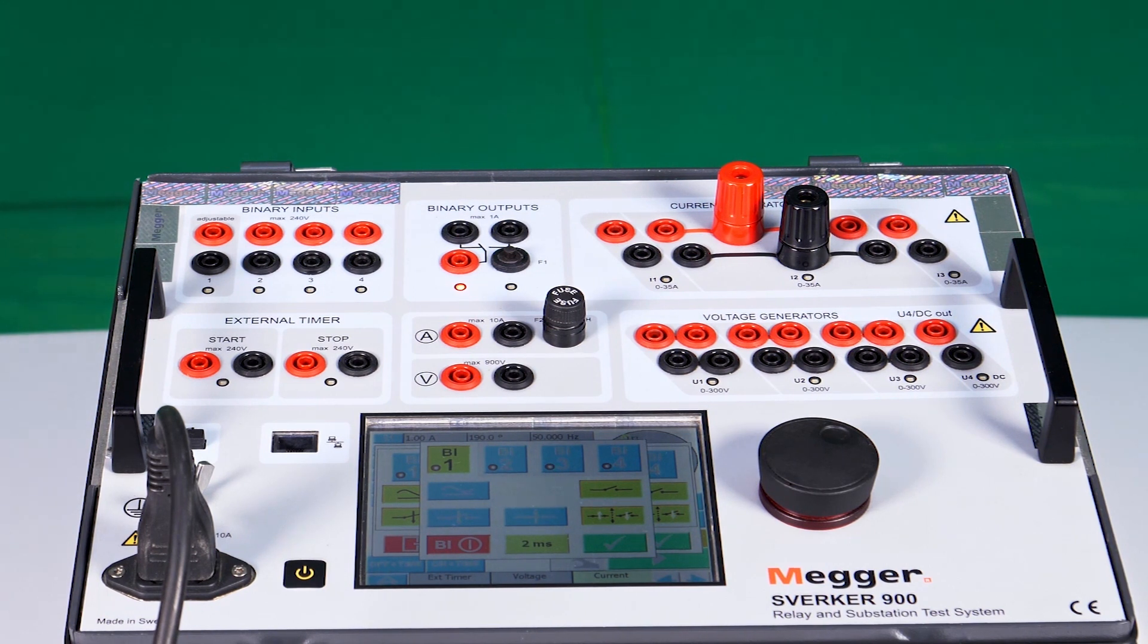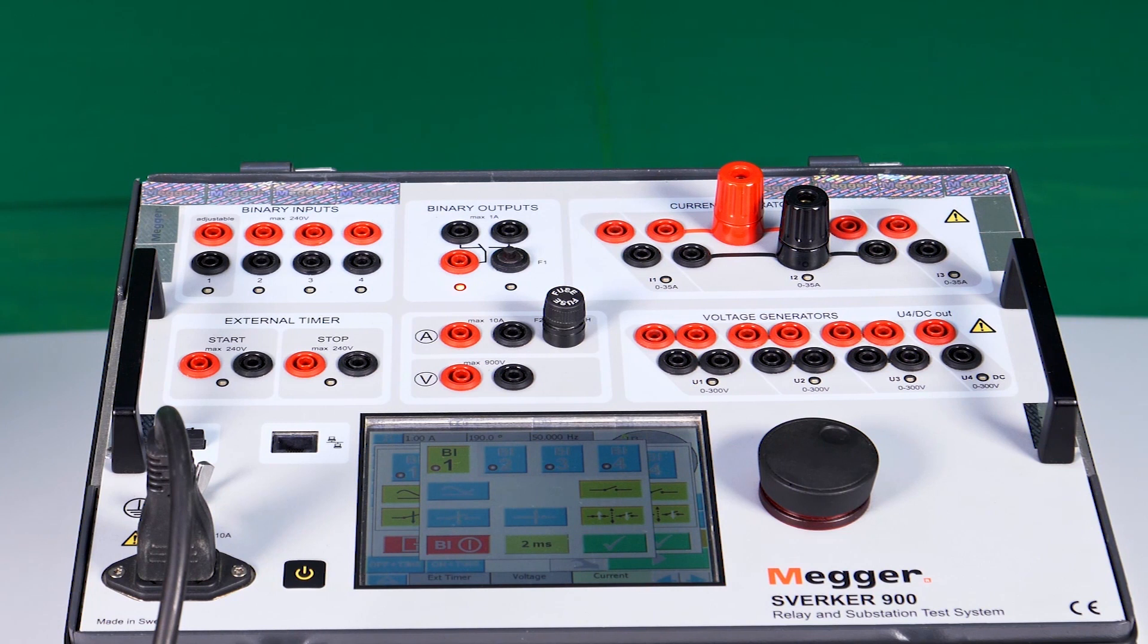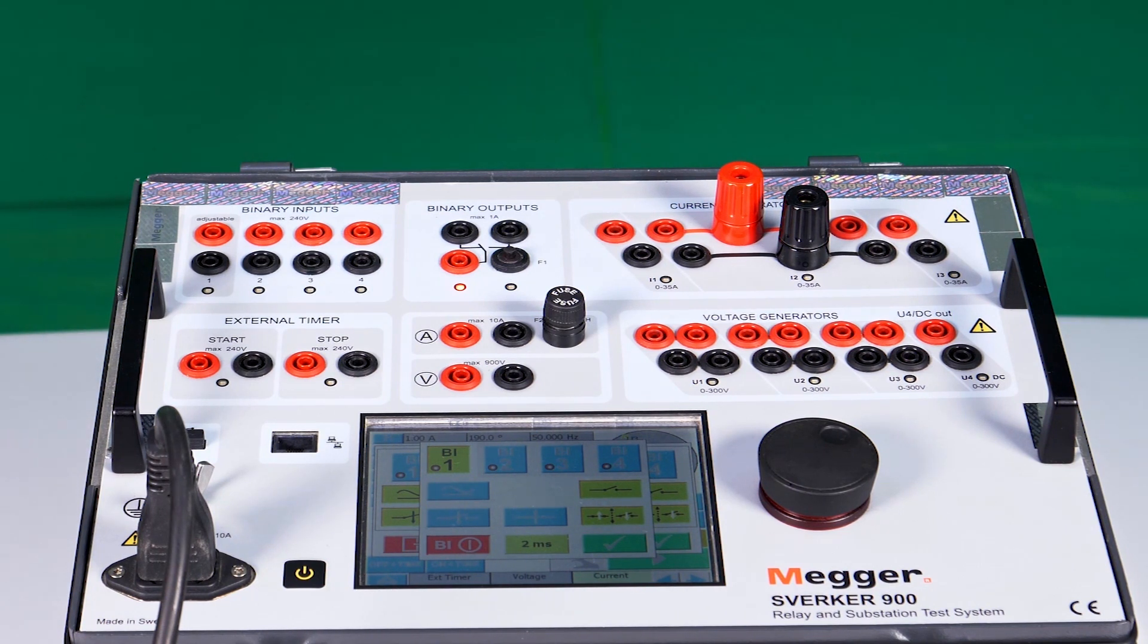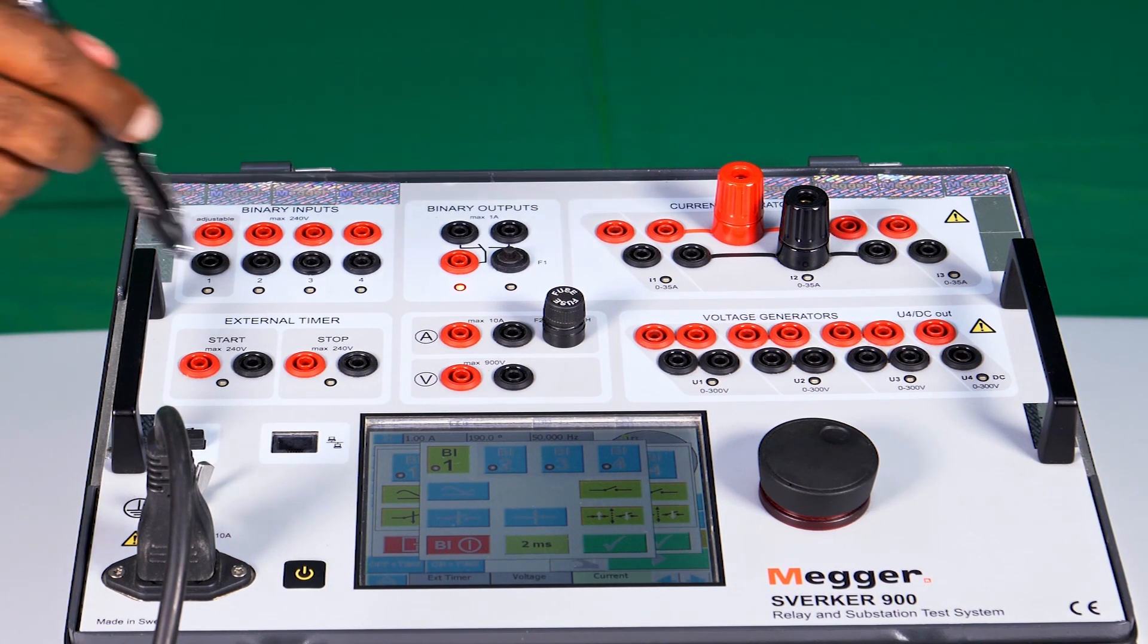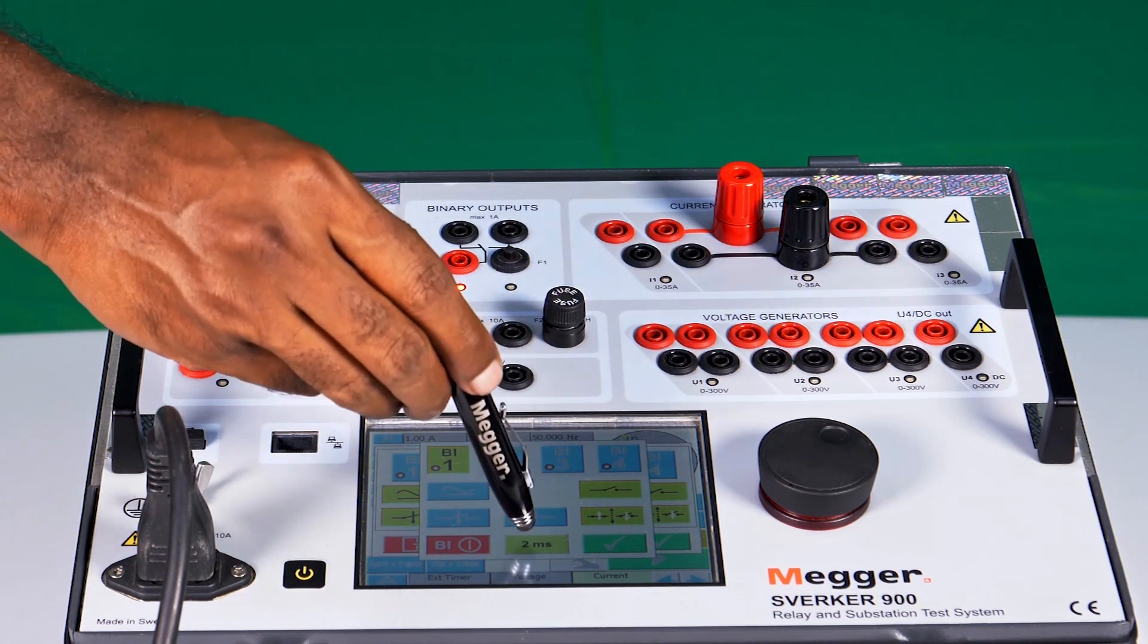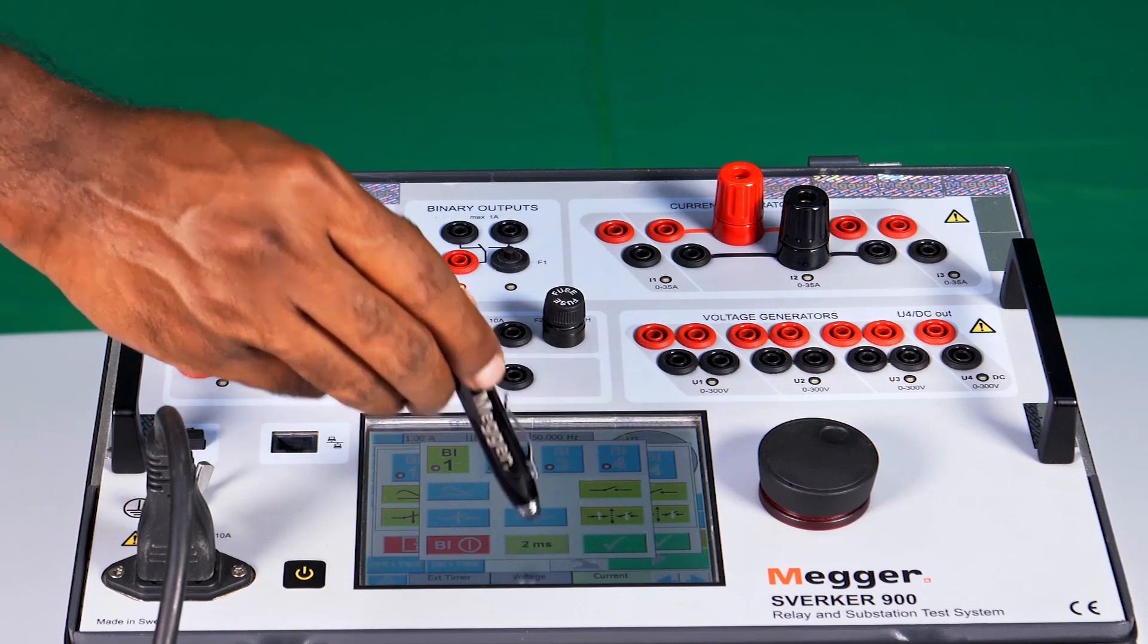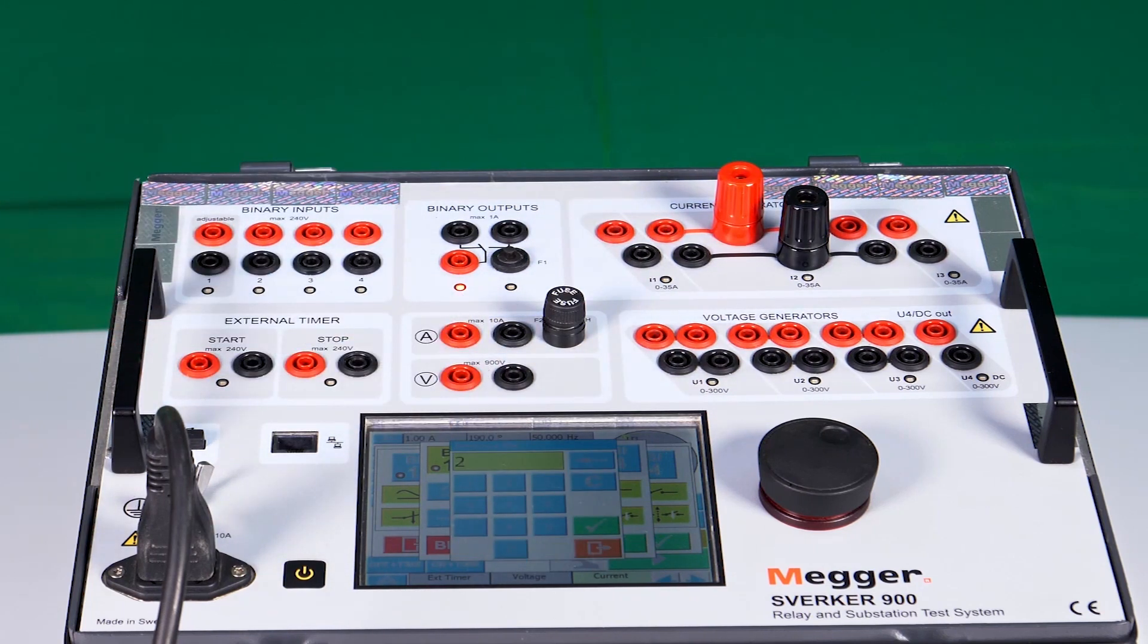In addition, each BI can also have a debounce timer, which can be configured from 0 to 999 milliseconds, to cope with the chattering of relay output contact. The same can be modified using this button.